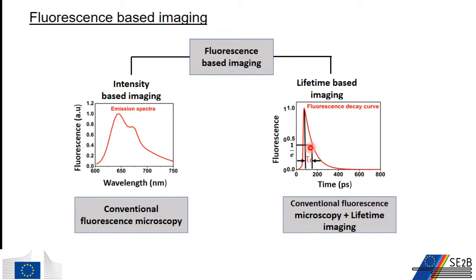In conventional fluorescence microscopy, the emission intensity of a specimen is integrated over time to create an intensity-based image of the sample. Spectral emission filters are used to separate the weaker emitted light from the much stronger illumination light. In the fluorescence lifetime imaging method, instead of recording the emission intensity, the decay of the fluorescence across the specimen is recorded and used to construct the image.